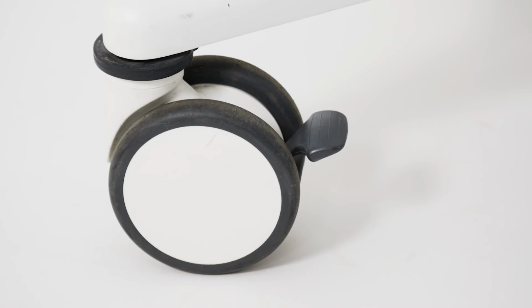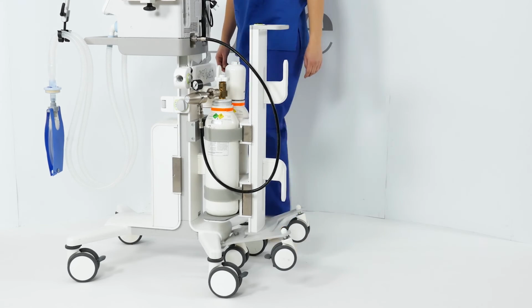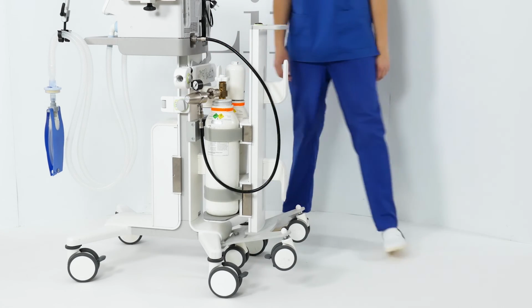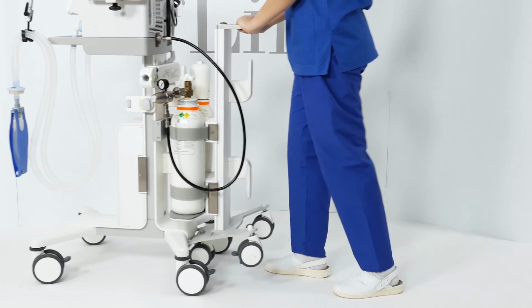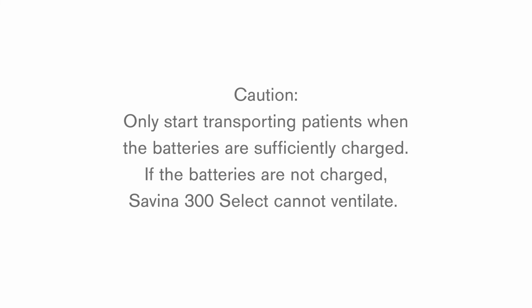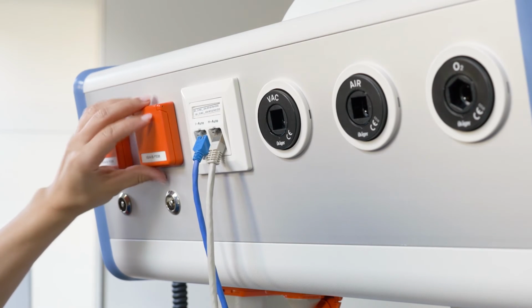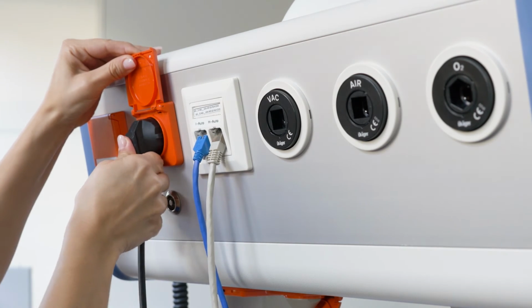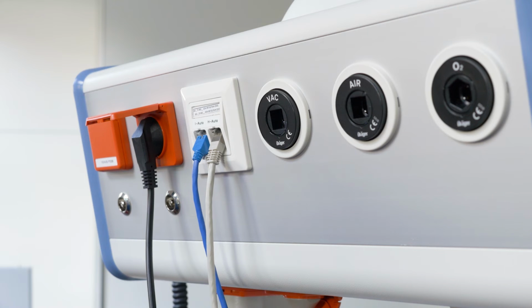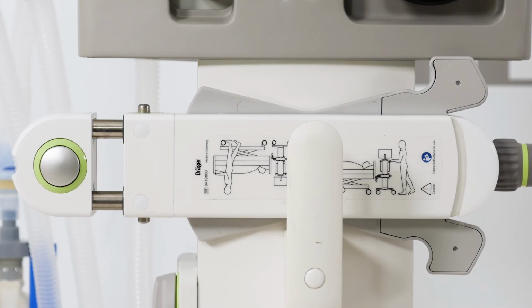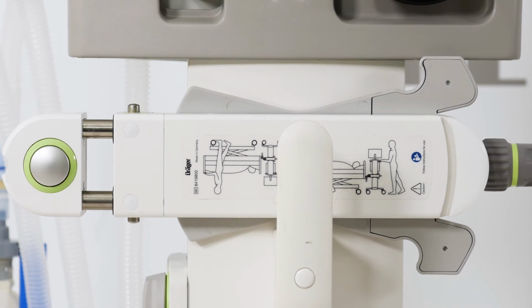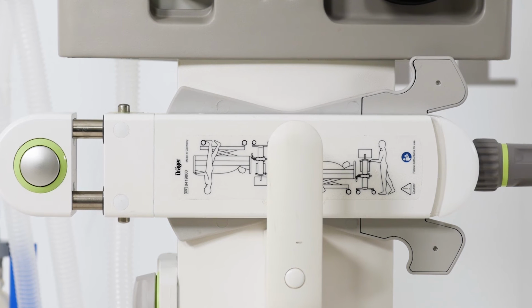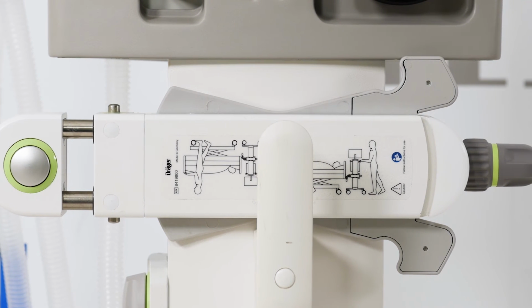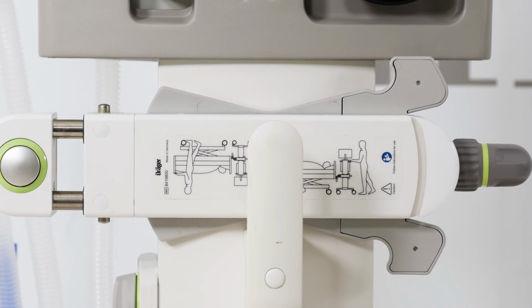Release all locking brakes and move the ventilator by the handle. Immediately reconnect the device to the mains power supply following patient transport to ensure that the batteries are being charged. For transporting patients, the trolley of Savina 300 Select can be coupled on a bed. It is a prerequisite that the device side coupling part is attached to the trolley.